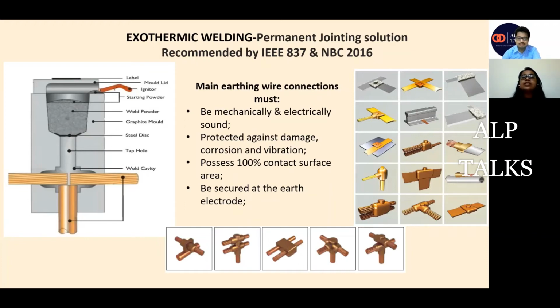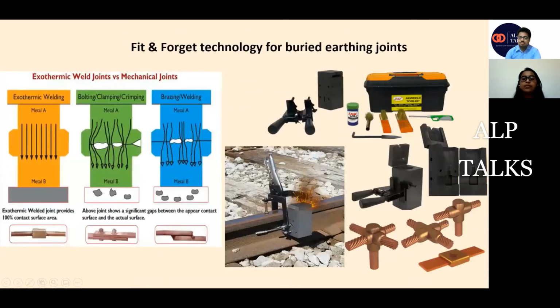That's why the standards are now recommending exothermic welding. Basically, it is a permanent jointing solution, and it is recommended mainly for underground earthing connections. The advantage of these joints is that they provide us 100% surface area. The cross section of the joint itself is much larger than the cross section of the conductor, so the life of the joint is also good. The joints are head-to-head joints. There is no overlapping between the conductors, so this is another advantage. It is a permanent solution, it will not corrode, so it will not fail after time too. So now the standards are recommending permanent welding solutions in place of nut and bolting or arc welding. Here the picture shows a railway track. That is exothermic welding.